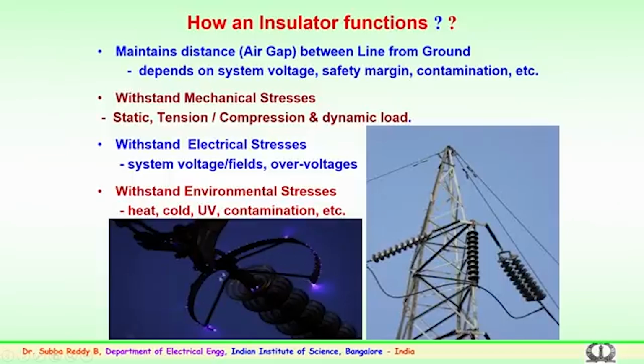The corona effect is a phenomenon which occurs near the vicinity of the conductor, where air breakdown takes place, and there are luminous discharges coming from the hardware if it is not properly designed. These discharges continuously hit the insulators, either ceramic, glass or porcelain. In the case of ceramic, there are not many issues, but in the case of polymer, these corona discharges which continuously hit the surface of the polymer insulators, which are organic in nature, are likely to degrade the surface and make it lose its hydrophobicity over a period of time. Flashover or further degradation is then likely, and the insulator may give way. We will be discussing this also when we come to the polymer insulator. So, these are all the various environmental stresses the insulators have to withstand in service.